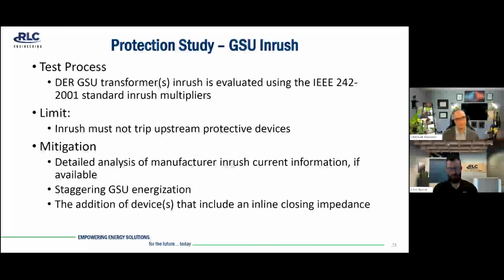And then my last slide here would be GSU inrush. We usually apply and look at the DER GSU transformers and evaluate it based on IEEE 242-2001 standard inrush multipliers. And the inrush must not trip the upstream protective devices. If we see that it is tripping upstream protective devices, I would say in a very small amount of cases, we may be able to shift the settings of one of those upstream devices. If it was a really borderline case, usually it's not.